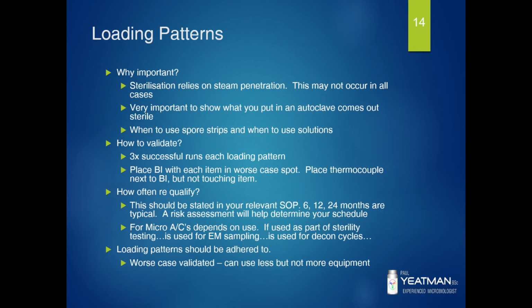Touching on spore strips versus solutions again. Spore strips are used when they can be placed in or next to a test item, like with this terminal sterilisation, or next to, say, an air sampling head in a micro autoclave, versus spore solutions when we want to have spores penetrate an item or get into the tight places, say down a centre cavity or stopper, possibly into the interior of a tube. But keep in mind that you need to flush out any solution in the tube post validation. If you can get a spore strip down there, then I'd do that, because you always chop it out of the tube afterwards.